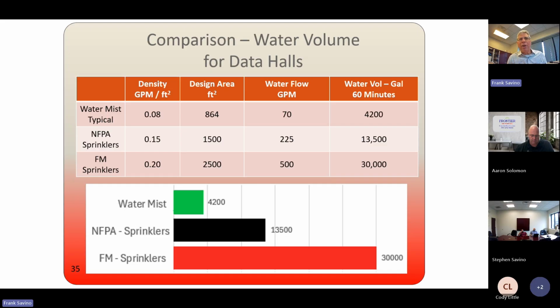That translates to 225 gallons a minute. So for 60 minutes, 13,500 gallons. The Factory Mutual requirement, and a lot of these big data centers are Factory Mutual, 0.2 density, design area 2,500, which translates to 500 gallons a minute. 60 minutes of flow is 30,000 gallons.